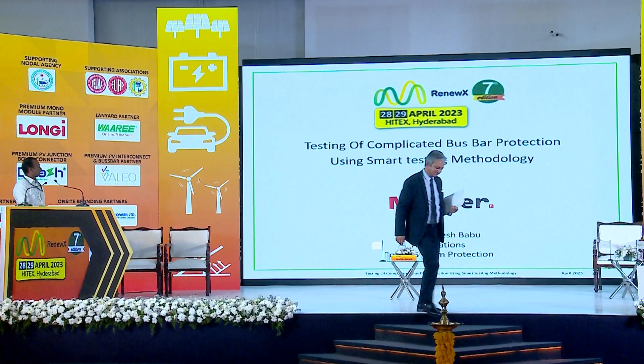Good afternoon, everybody. So, bus bar protection is one area where the application is very complicated, because when we have a grid connected system and the protection system operates, it has the tendency to even pull the entire system out of the grid. So this has to be tuned in such a way that there is no unwarranted operation. If there is any fault, it has to operate, and if there is no fault, it should not operate.